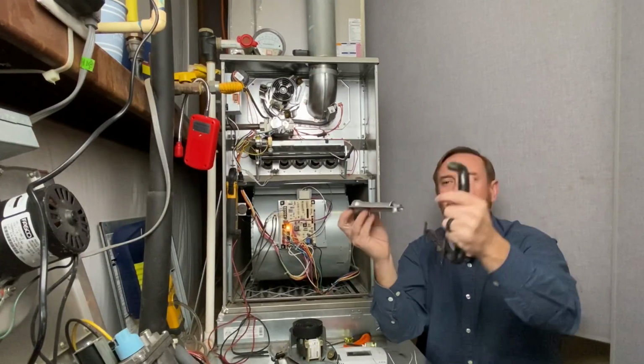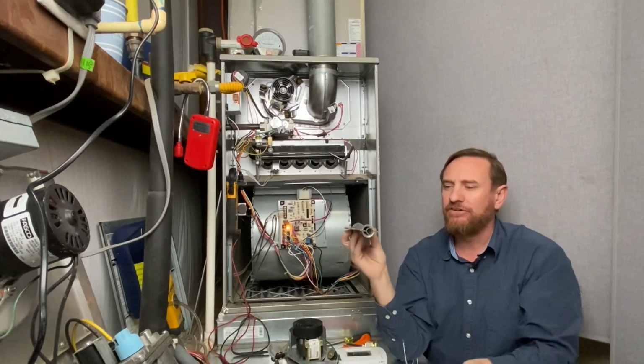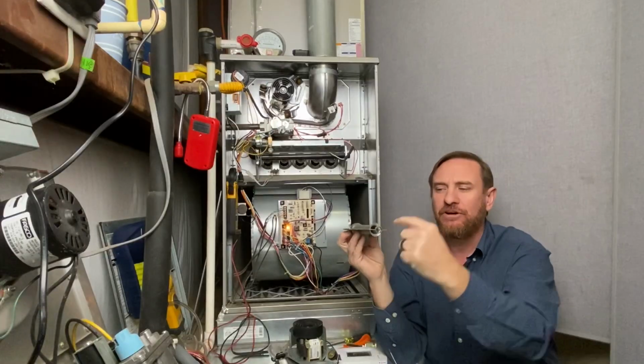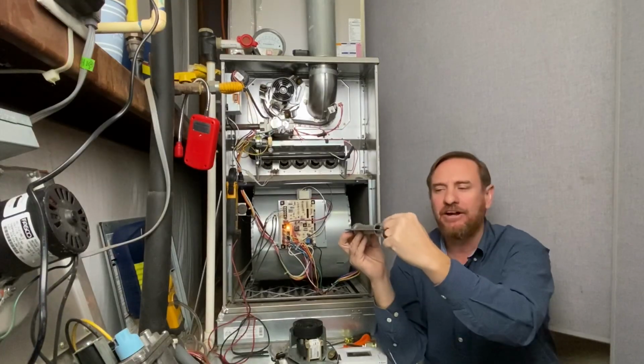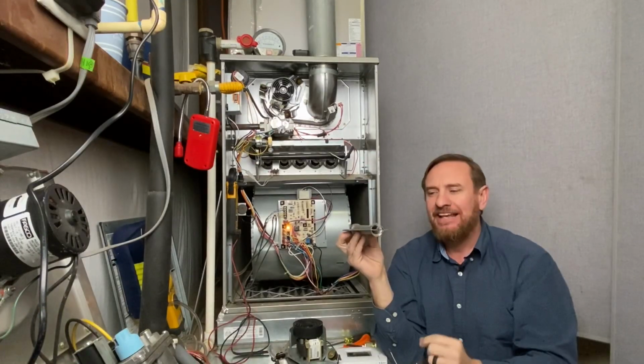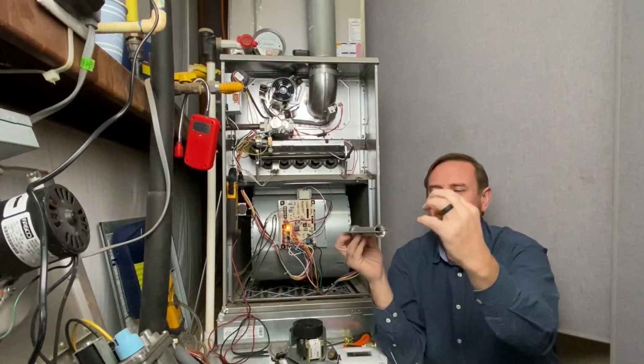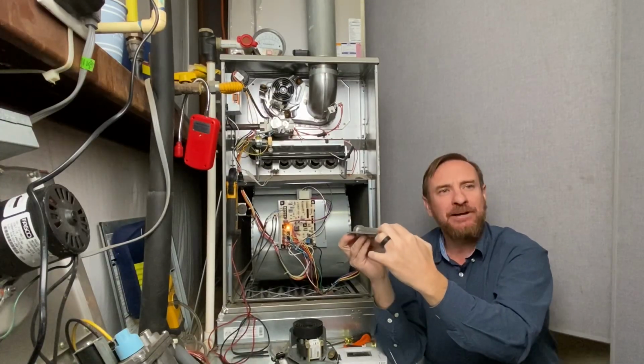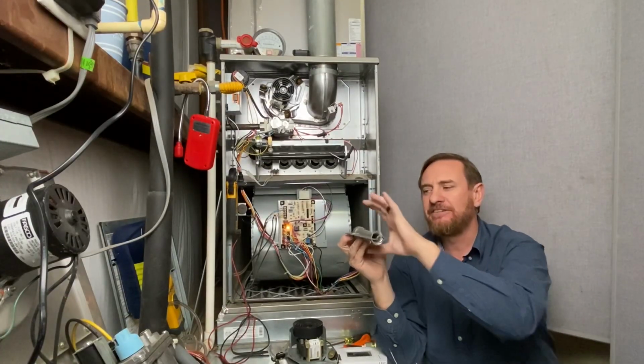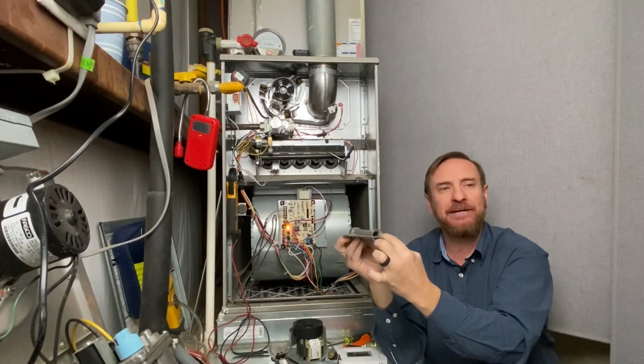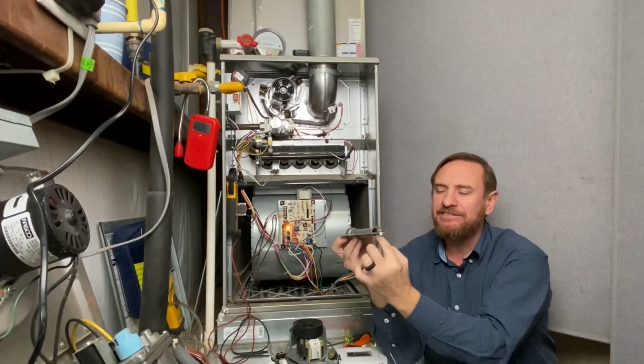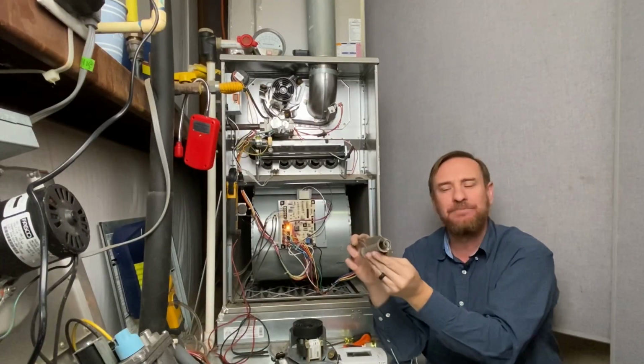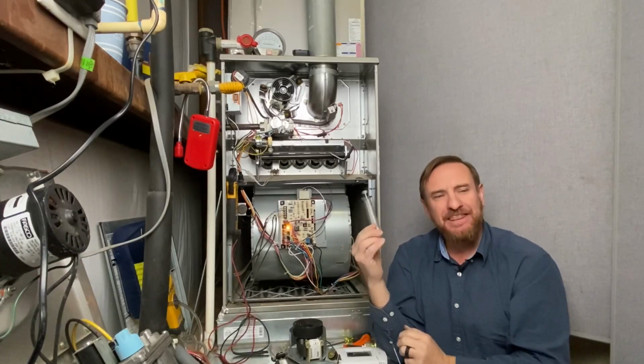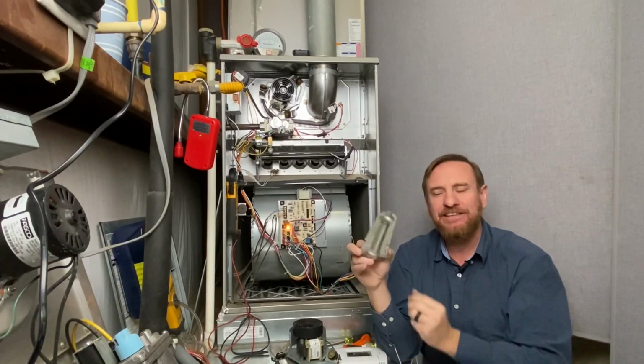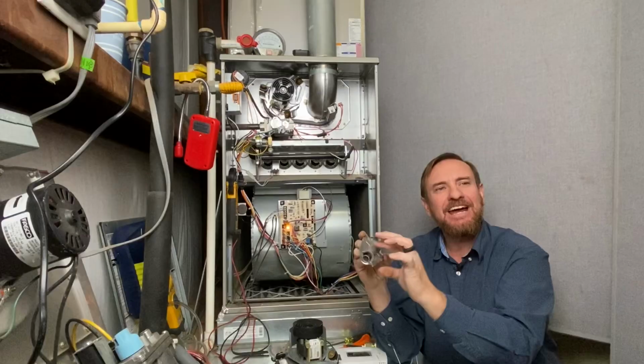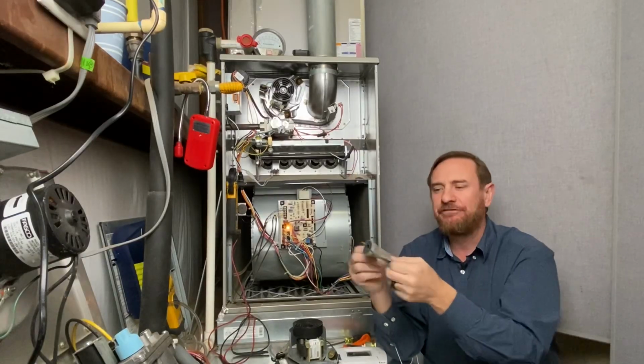Now if you notice, it's shooting gas to the very center of this hole. As it shoots gas to the center of the hole, it's actually pulling air in around it. This effect right here is it's shooting the gas in, it's pulling air. This is primary air, not just air. We have two kinds of air: secondary air burning around it and primary air. That primary air needs to mix with the gas inside this burner. Burners do two jobs. They mix the air and the fuel, and they direct the flame. So here we're mixing the air and the fuel, and then we're directing the flame coming out.